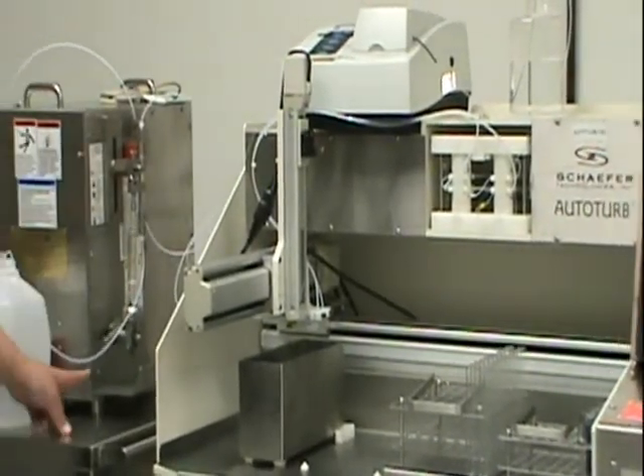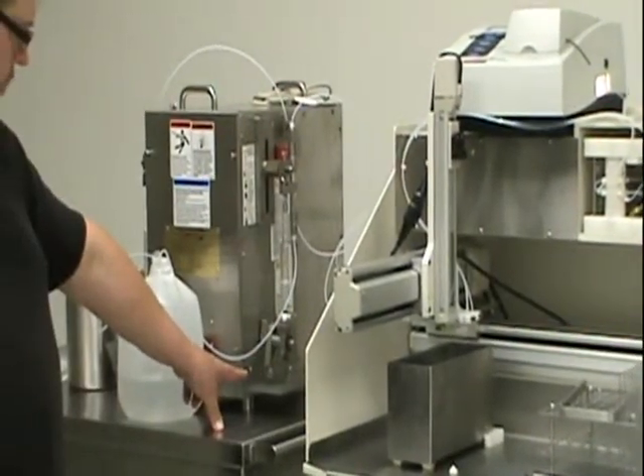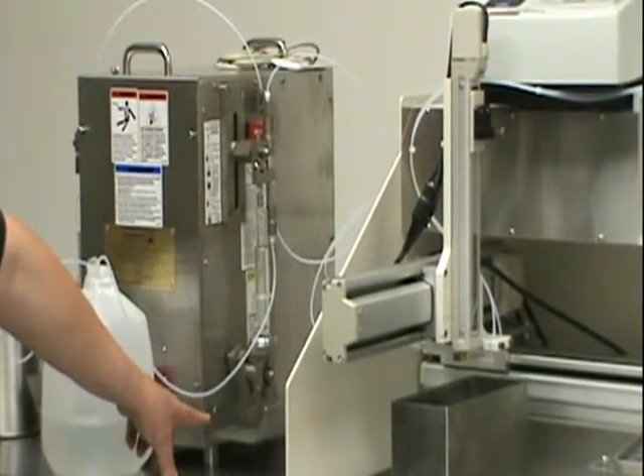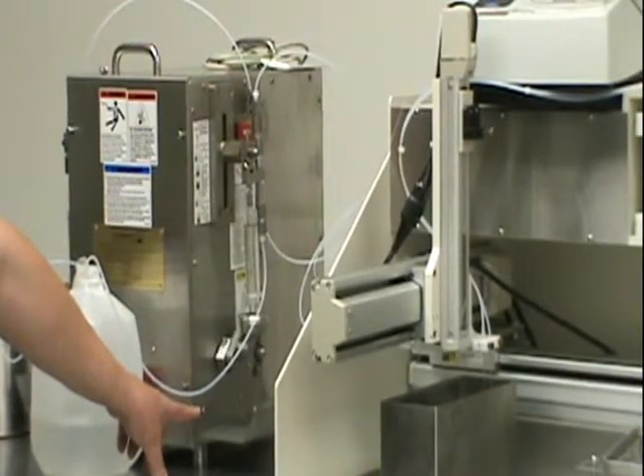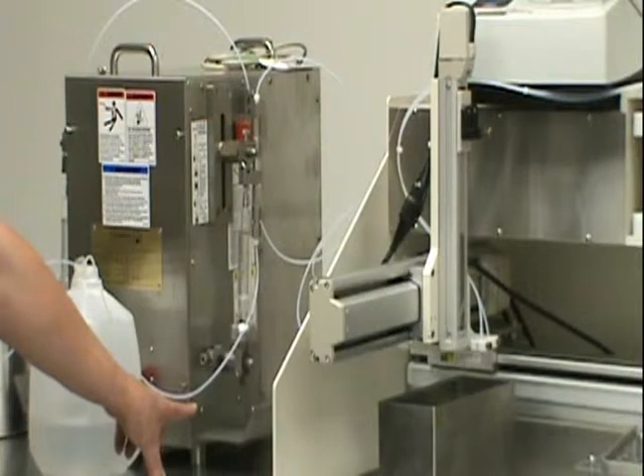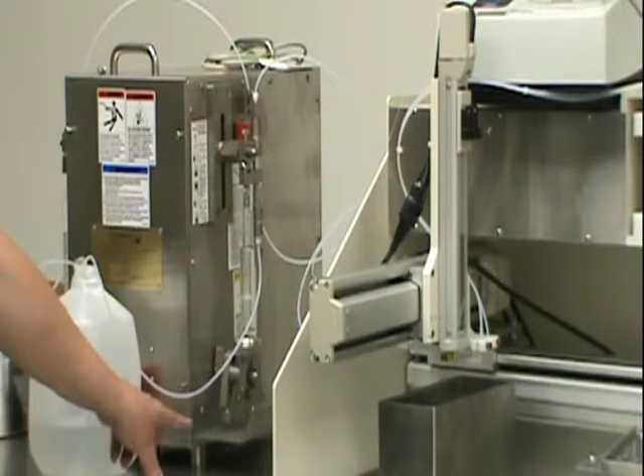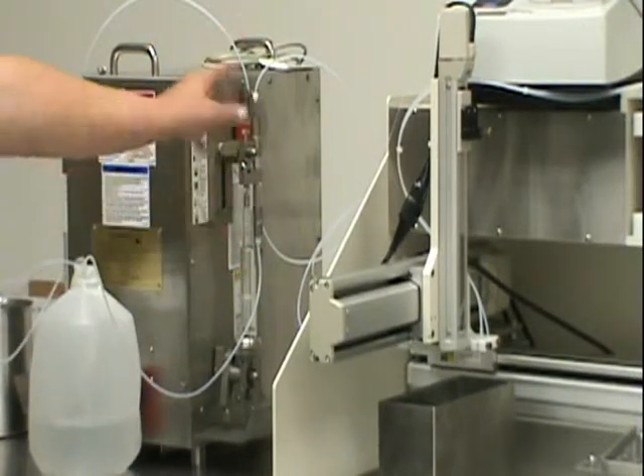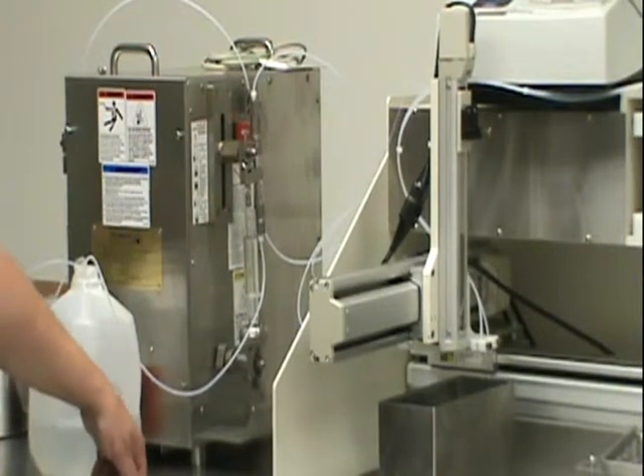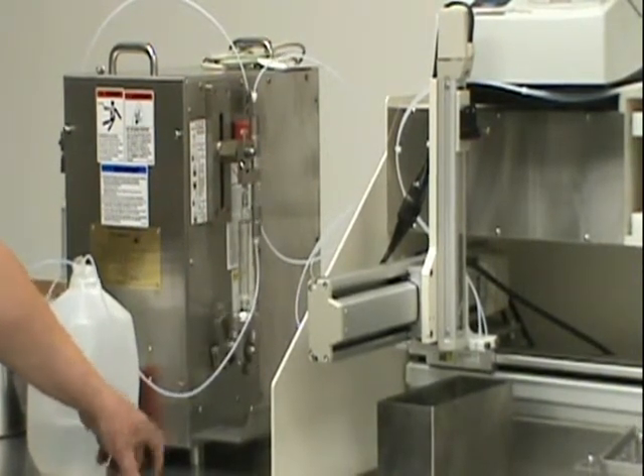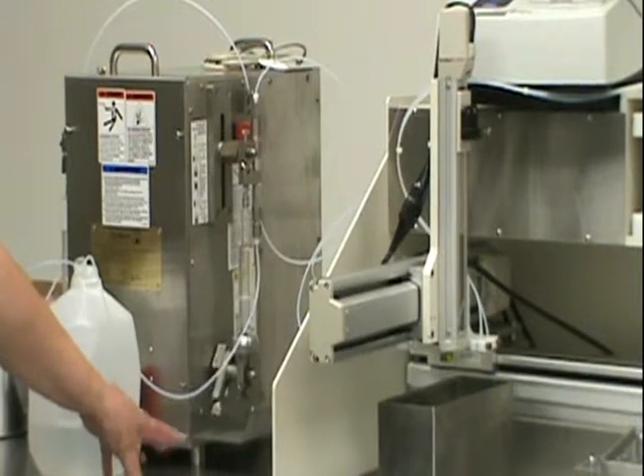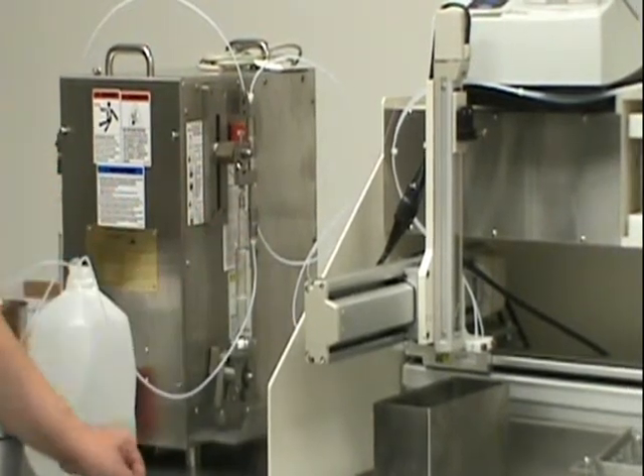And there should be approximately half a second to a second delay, or a little bit longer when that stops to when it starts again. If it's too fast, this system won't fully fill with liquid, the volumes will be off. So we have to give it that pause time to dwell long enough to fill, make sure that it's stabilized.